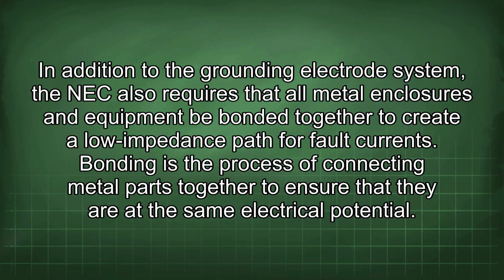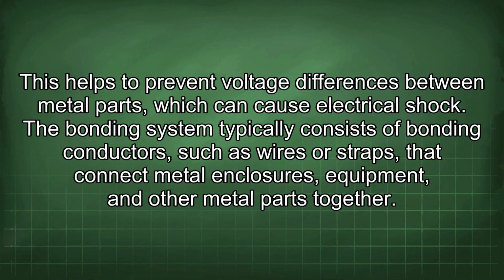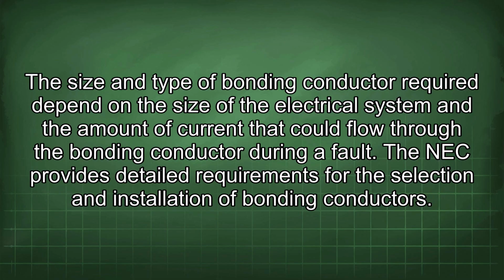In addition to the grounding electrode system, the NEC also requires that all metal enclosures and equipment be bonded together to create a low impedance path for fault currents. Bonding is the process of connecting metal parts together to ensure that they are at the same electrical potential. This helps to prevent voltage differences between metal parts, which can cause electrical shock. The bonding system typically consists of bonding conductors, such as wires or straps, that connect metal enclosures, equipment, and other metal parts together. The size and type of bonding conductor required depend on the size of the electrical system and on the amount of current that could flow through the bonding conductor during a fault. The NEC provides detailed requirements for the selection and installation of bonding conductors.